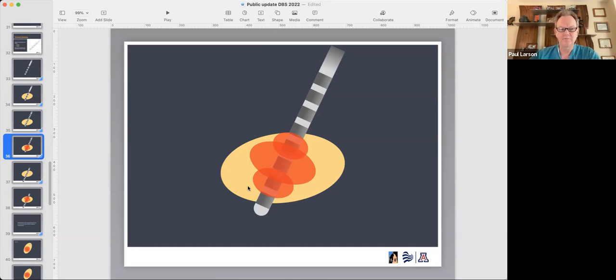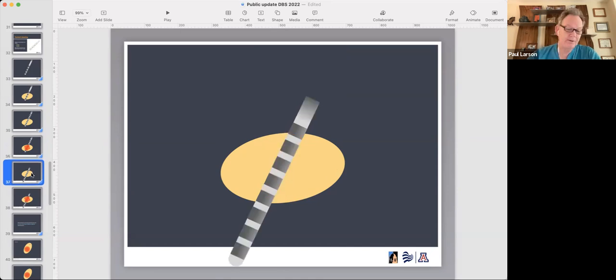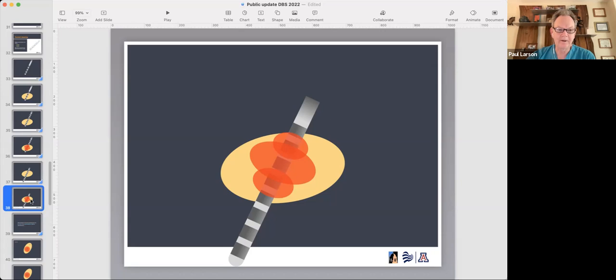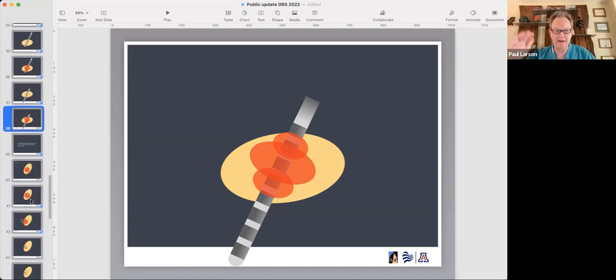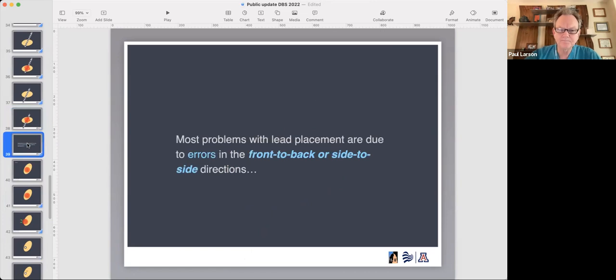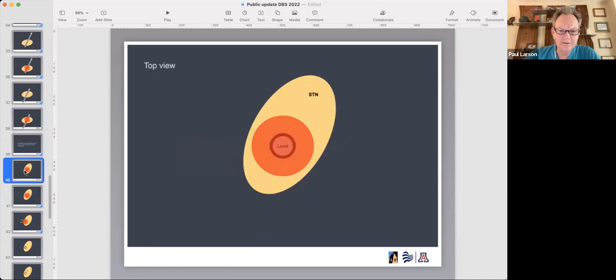so you can shape the stimulation vertically. If this electrode happens to be a little bit deeper, let's say the surgeon put it a little bit deeper, and this might be just a millimeter difference in depth, but that can make a big difference in how we stimulate. We can simply use these upper electrodes. So this is a wider spaced electrode array, if you will, and that allows us to direct current up and down. Most of the time, however, we have problems if the electrodes are not exactly in the middle of the target and they're either a little bit in front or back, or a little bit one side to the other within the target. So let's look at an example of that.